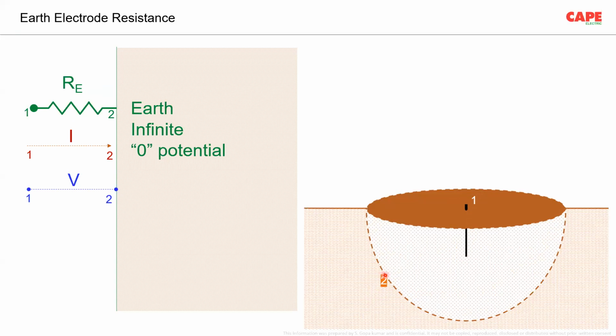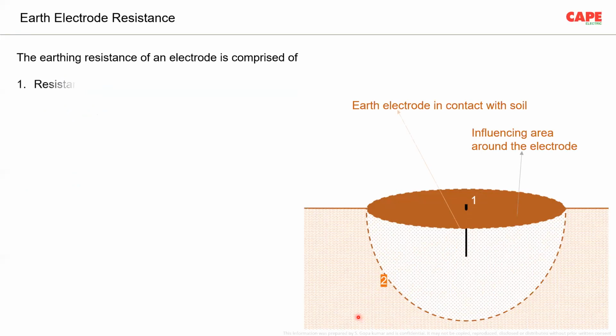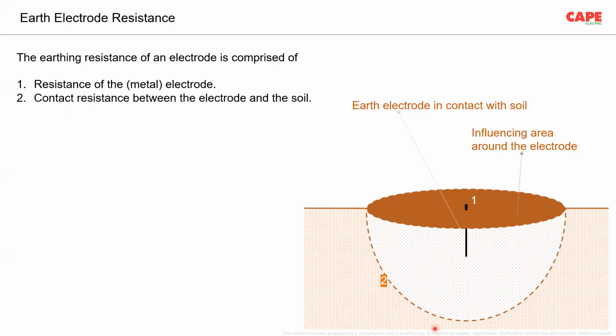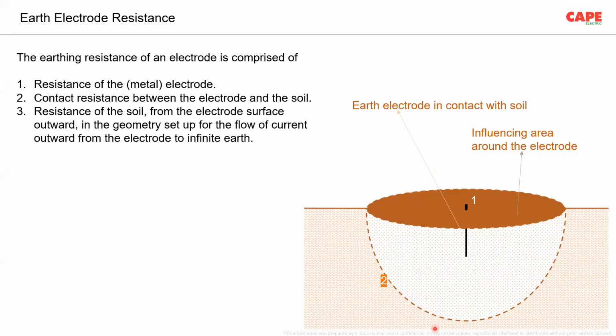So basically, the electrode resistance which we are talking about, you can see here there is an earth electrode, there is an influencing area around the earth electrode, and the resistance RE which we say consists of 3 factors. Number 1, the resistance of the earth electrode itself. Imagine you have a 3-meter rod having some milliohms or some micro ohms resistance. Number 2, the contact resistance between the electrode and the soil. The third one is the resistance of the soil from the electrode surface outward, in the geometry setup for the flow of the current outward from the electrode to infinite earth. So the third factor, which is nothing but the soil in between the earth electrode and the infinite earth, these 3 factors are going to influence the resistance RE.